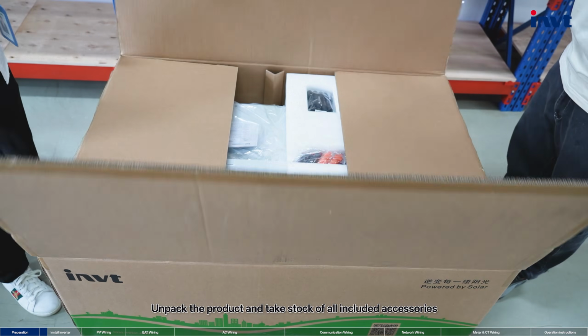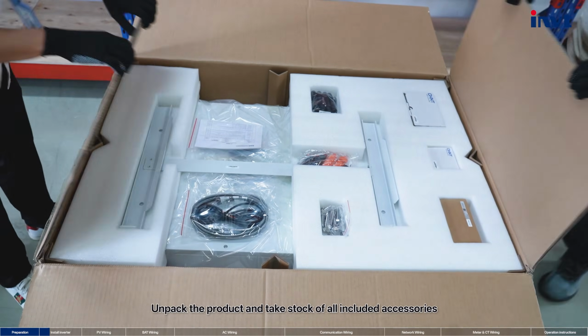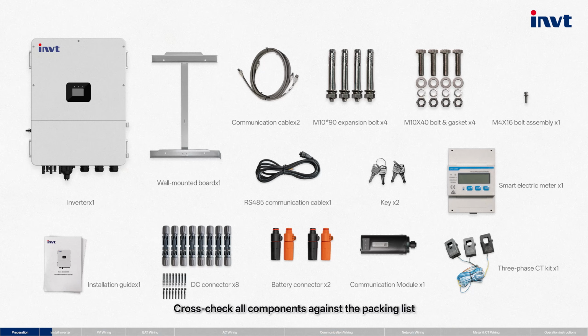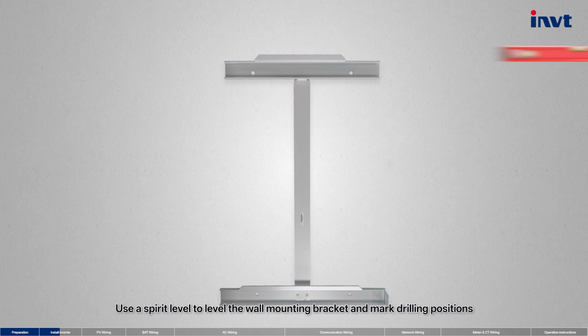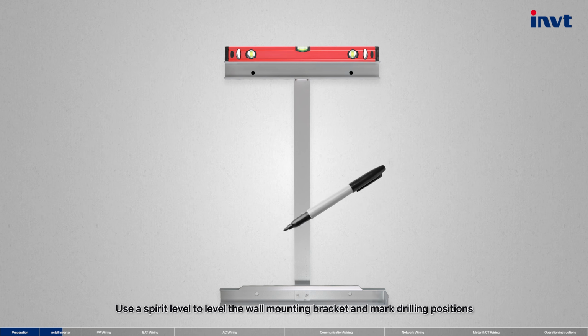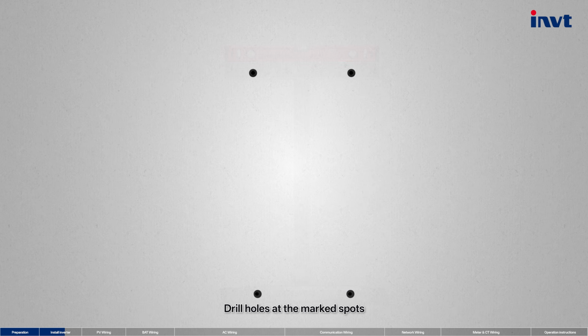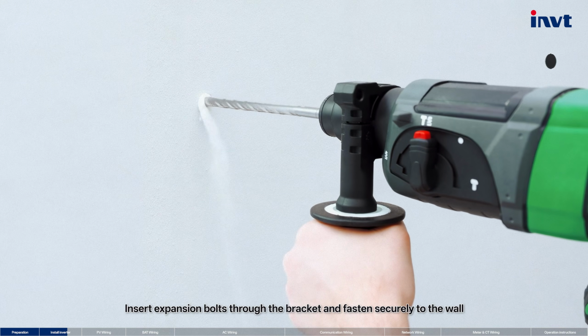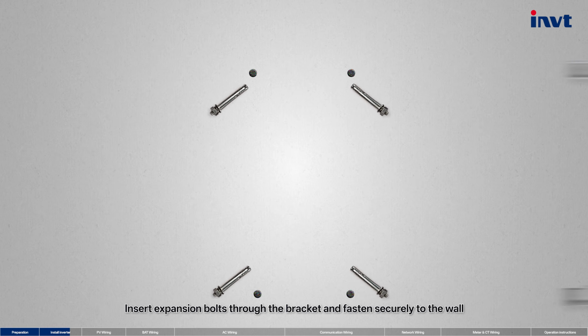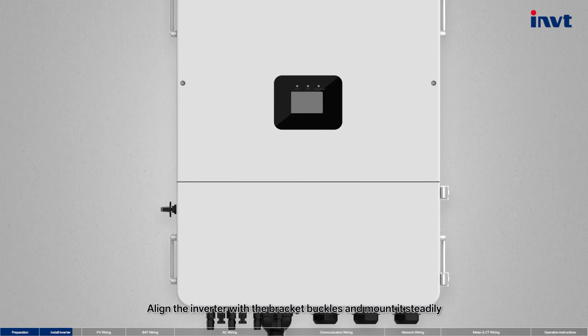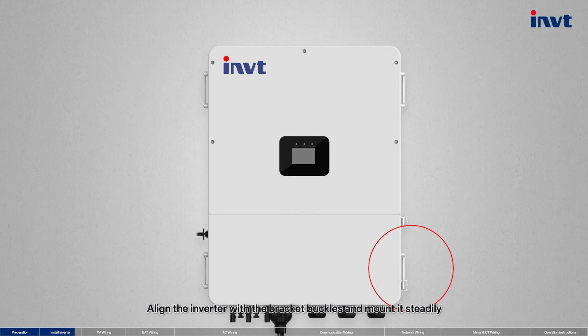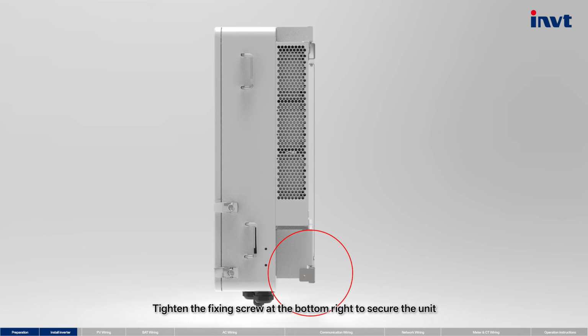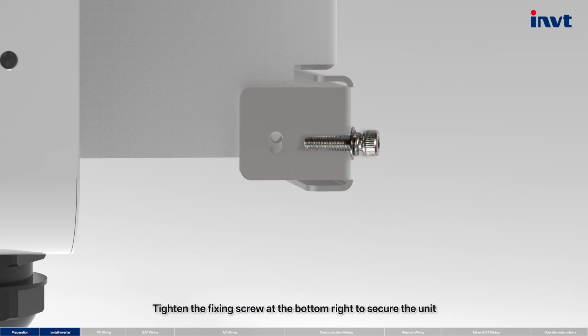Unpack the product and take stock of all included accessories. Cross-check all components against the packing list. Use a spirit level to level the wall mounting bracket and mark drilling positions. Drill holes at the marked spots. Insert expansion bolts through the bracket and fasten securely to the wall. Align the inverter with the bracket buckles and mount it steadily. Tighten the fixing screw at the bottom right to secure the unit.